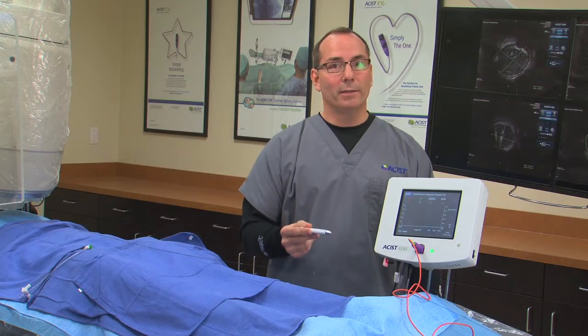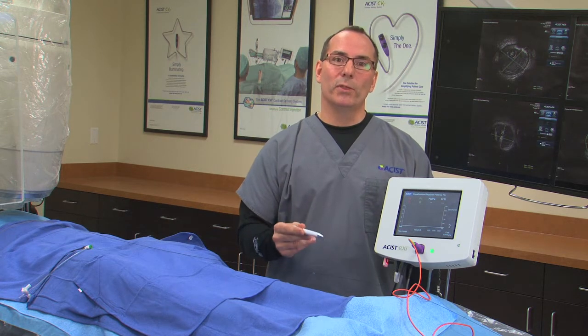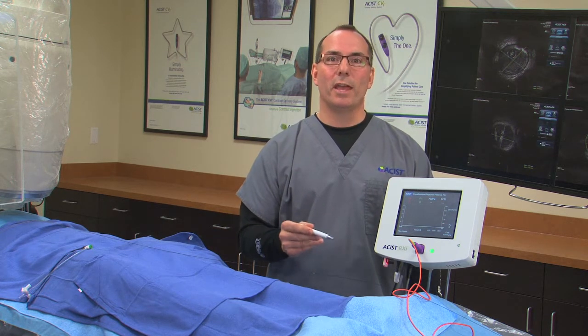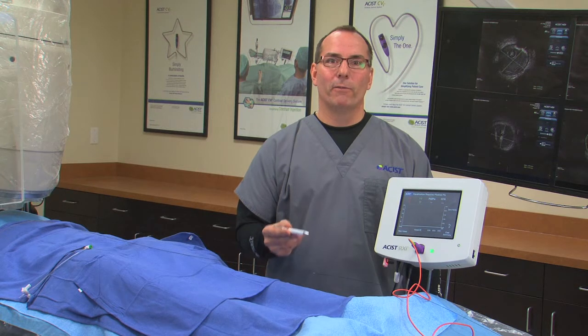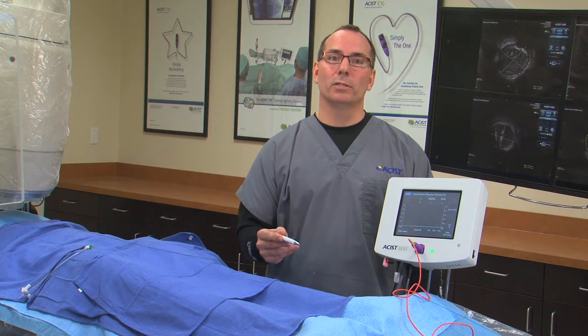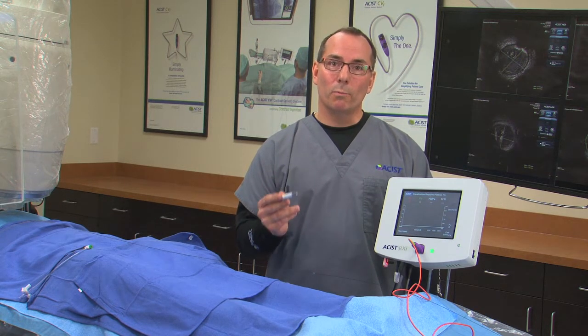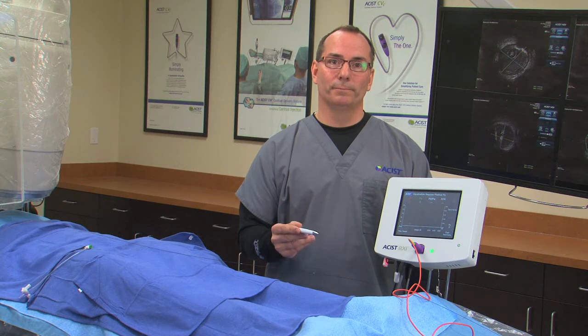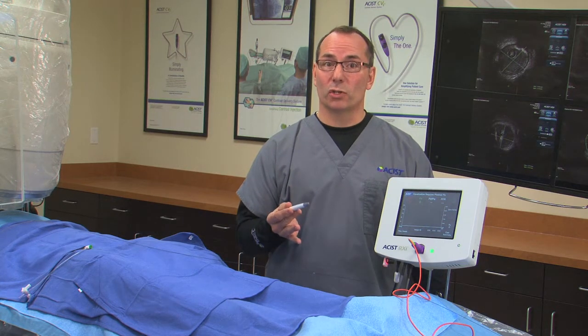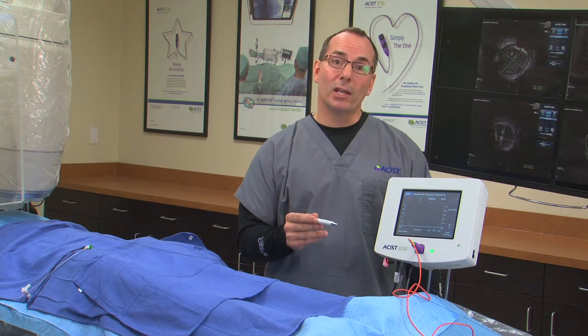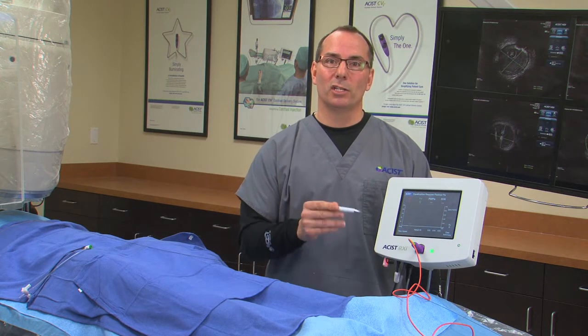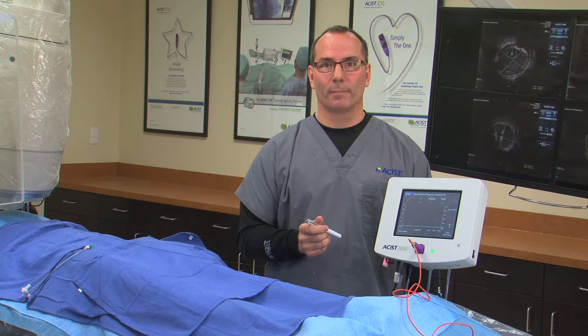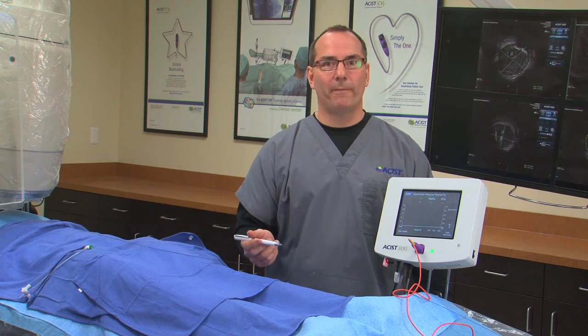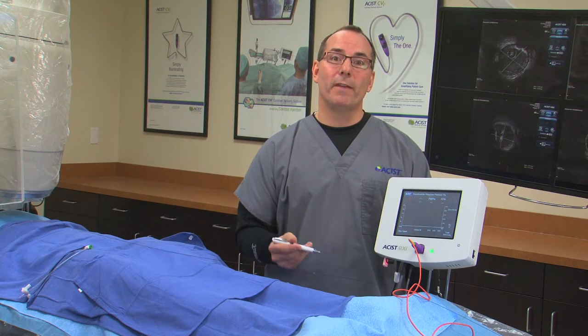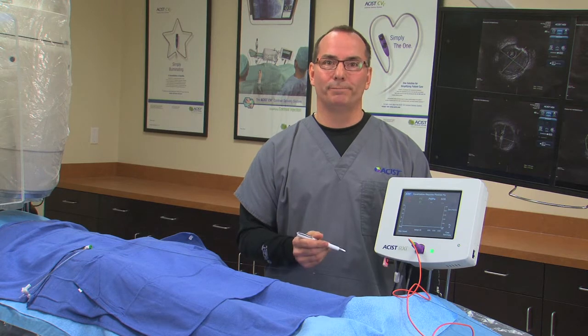Now PV allows the user to input a central venous pressure into the FFR calculation. For an accurate FFR, it's important to remove the resistance to blood flow. A high venous pressure increases resistance to blood flow, therefore a PV value should be used in the calculation of FFR. The Rxi is the only FFR system in which the PV value can be easily input.